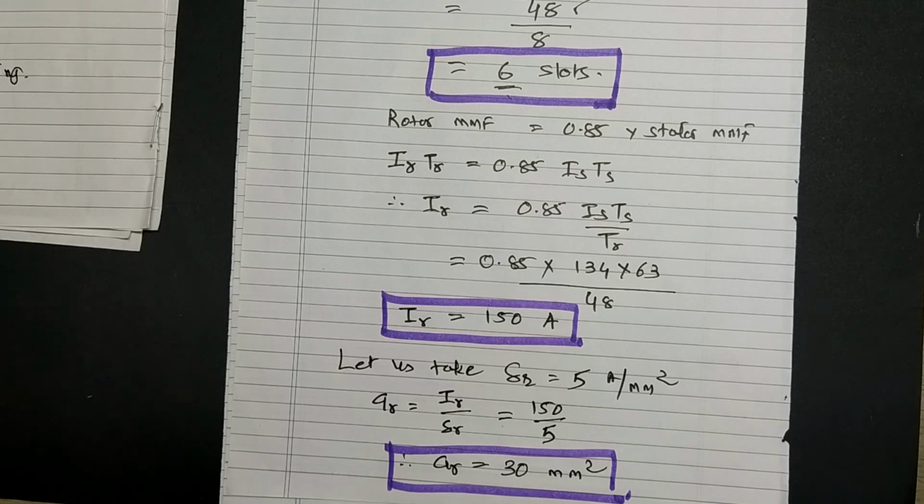Before that we estimated the rotor number of turns, then rotor slots, then based on the rotor slots, conductors per slot in case of rotor, then actual rotor turns, then there was a constraint of maximum voltage between slip rings, and at last the coil span of rotor side, that is important. So in this very simple way we have designed our slip ring type of rotor.